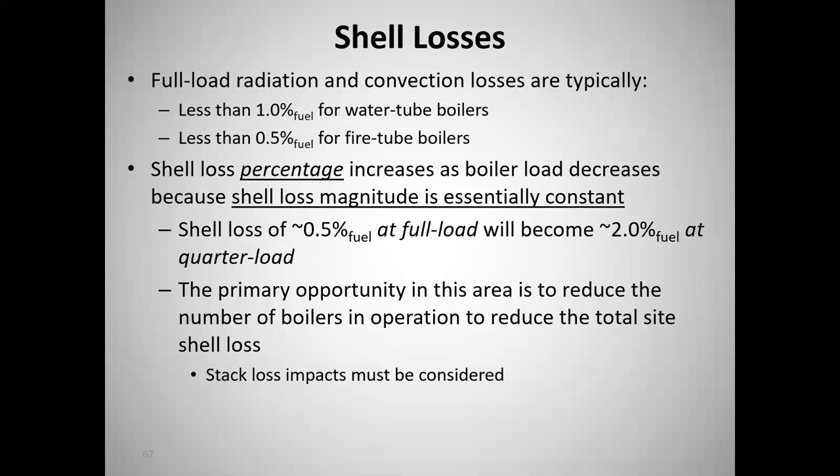So engineer Glenn comes in, sees all this, and calculates you can save $30,000 a year in shell loss if you, I don't know, go from 3 to 2 or 2 to 1, I don't remember, because the steam load was relatively small even for 1 boiler, and they were running multiple boilers. I said, well, this is an easy $30,000. And they looked at me and they said, no way. No way are we going to do that.